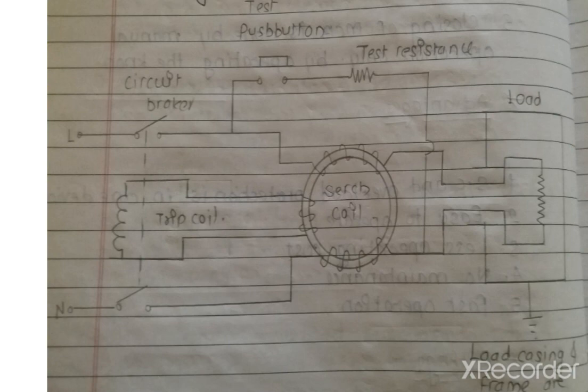ELCB provides protection to human beings if a human being touches the faulty devices. The test button used here is for checking the continuity of the ELCB. If the test button is pushed, the leakage current flows directly from the phase to the neutral, which operates the earth leakage circuit breaker. This is it for this lecture.